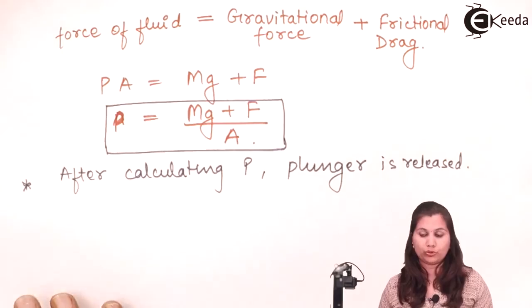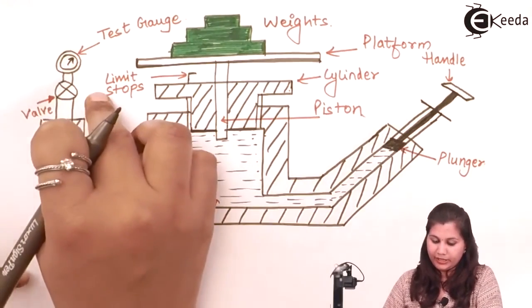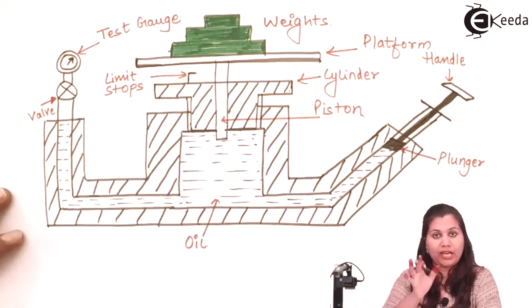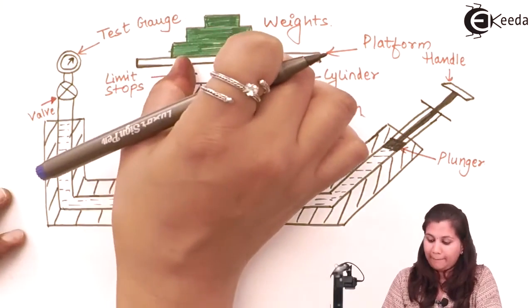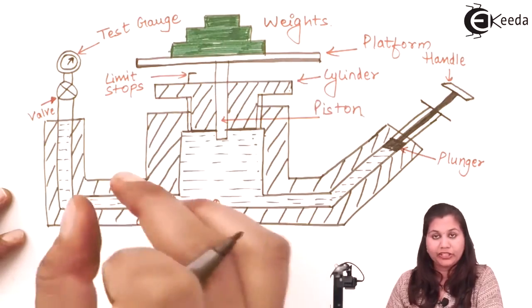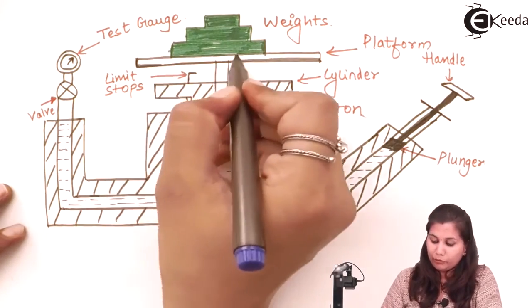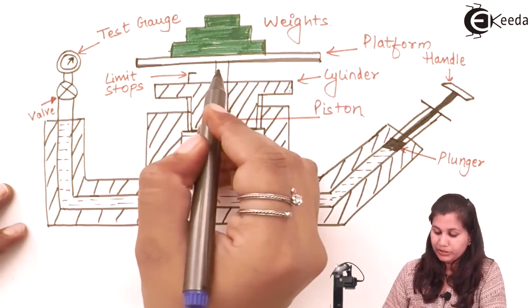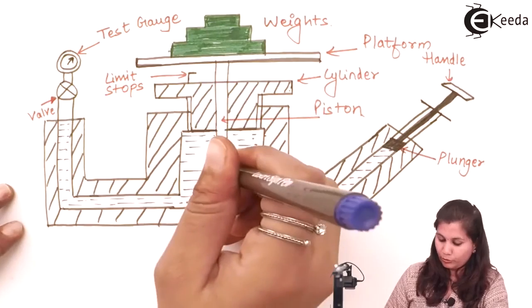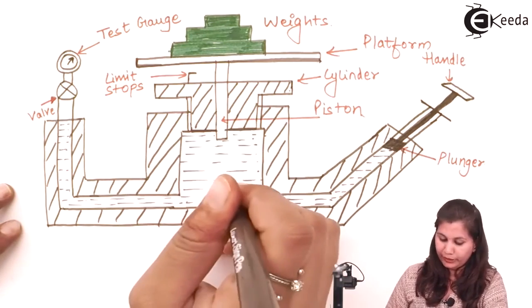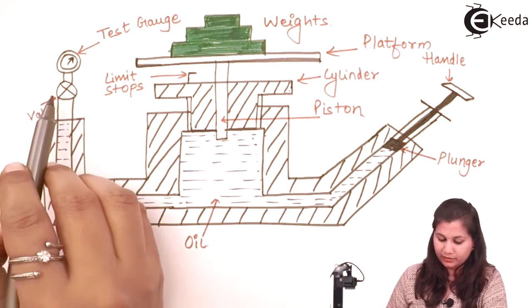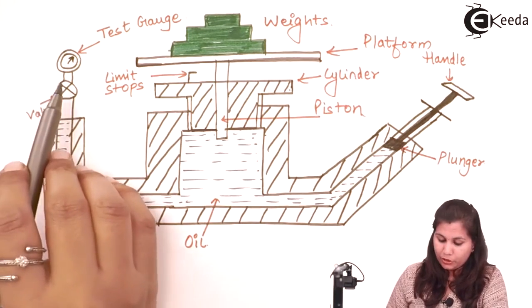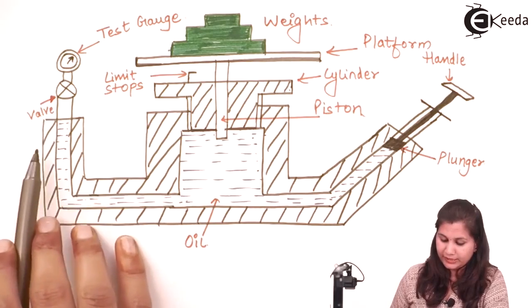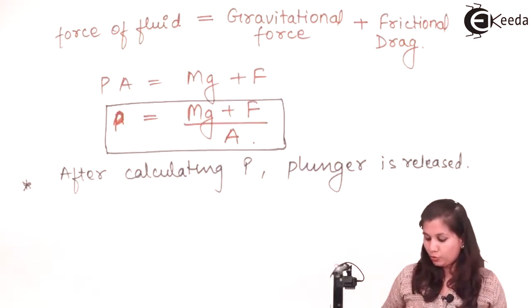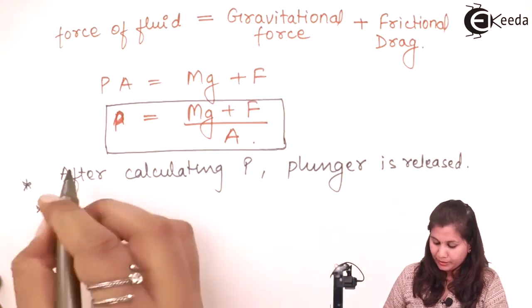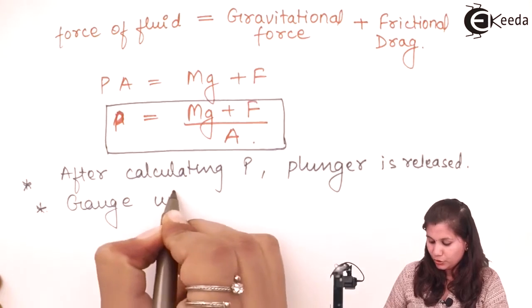Now the pressure gauge which we want to test is being connected with the dead weight tester. Now again the same amount of weight which we have placed earlier is being placed on the platform, and for that we have already calculated the pressure. Now due to this weight, the piston is going to move downwards, and it is going to exert a pressure over the fluid. Now the valve in this apparatus is being opened, so that the fluid pressure is being transmitted to the gauge. Okay, so after calculating P, the plunger is being released, and the gauge which is to be calibrated is connected.